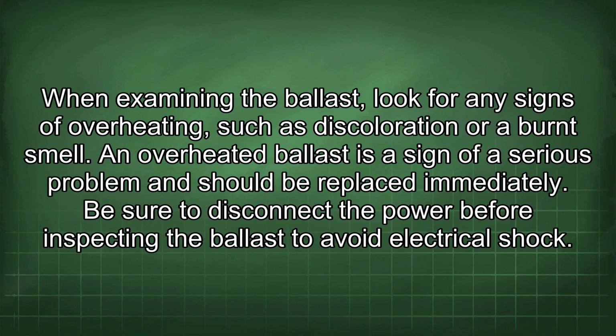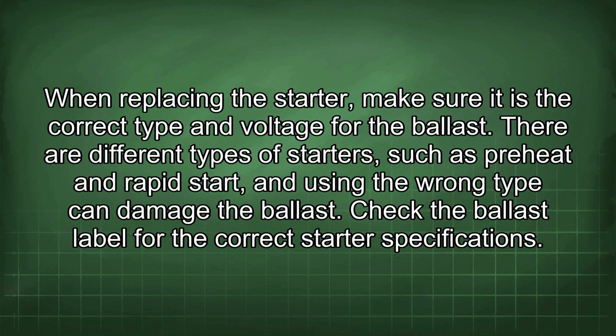When examining the ballast, look for any signs of overheating, such as discoloration or a burnt smell. An overheated ballast is a sign of a serious problem and should be replaced immediately. Be sure to disconnect the power before inspecting the ballast to avoid electrical shock. When replacing the starter, make sure it is the correct type and voltage for the ballast. There are different types of starters, such as preheat and rapid start, and using the wrong type can damage the ballast. Check the ballast label for the correct starter specifications.